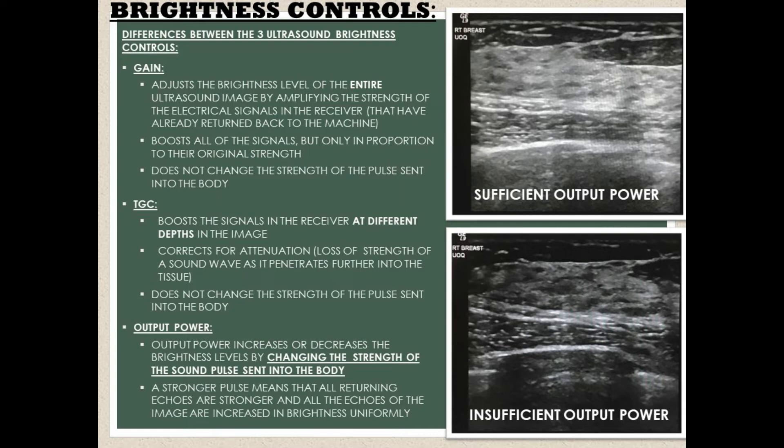The TGC control, or time gain compensation, boosts the signals in the receiver at different depths in the image. TGC corrects for attenuation — the loss of the strength of a sound wave as it penetrates further into the tissue.